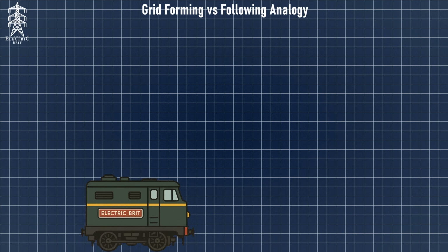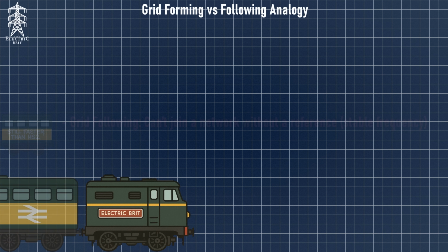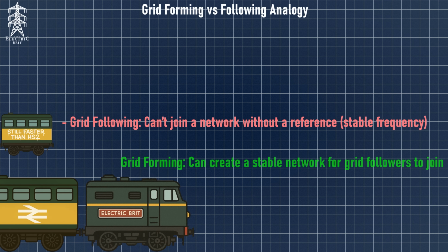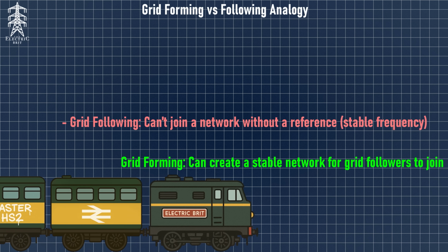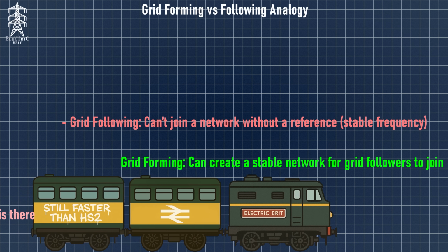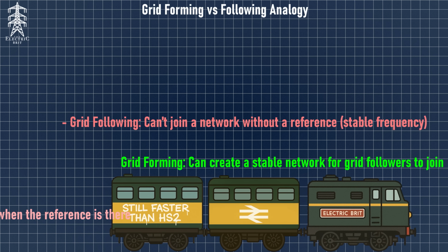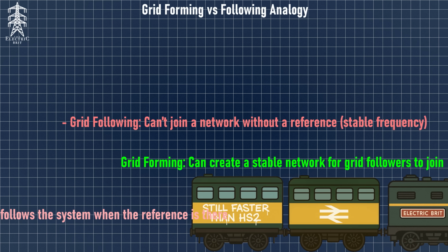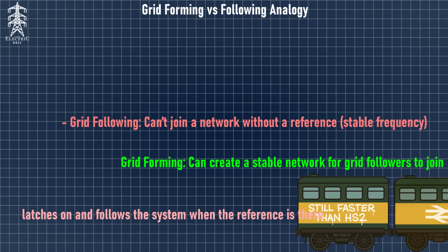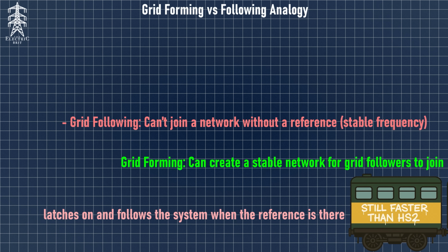Grid forming means that instead of needing a live grid to latch onto, these generators can create their own stable 50Hz voltage and frequency, just like a traditional spinning turbine would. You can think of it like a train. You first need a locomotive, a generator, that can set the speed and direction for the whole grid. Without that engine, the carriages, or grid following devices like traditional wind and solar, can't move at all. Only once a stable reference exists can they latch on and follow the system.